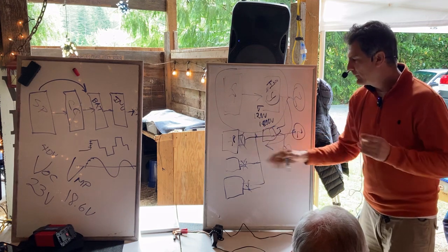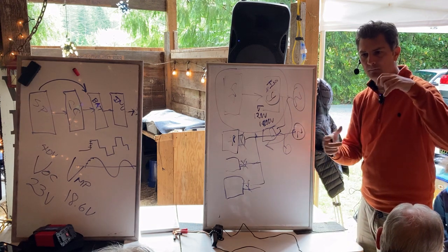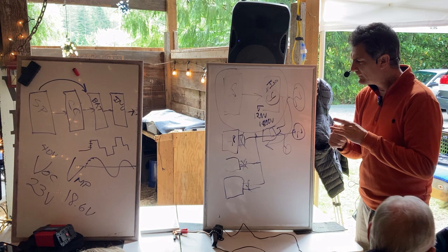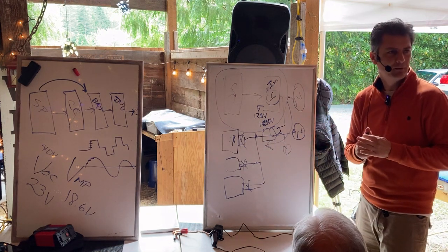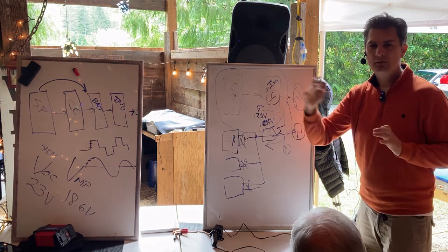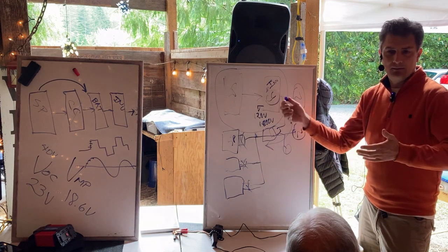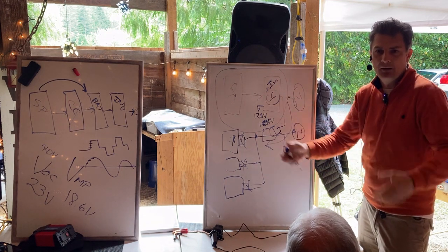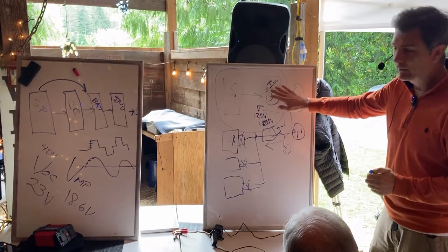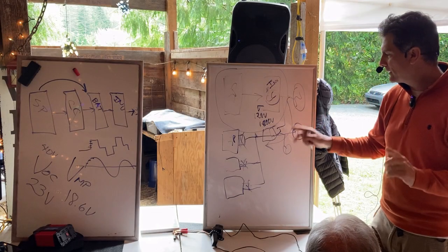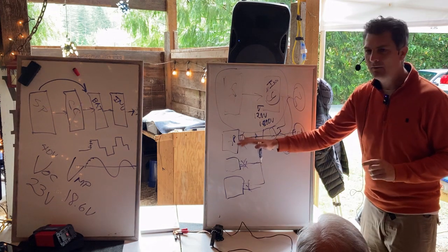The other thing is, if a microinverter breaks, you have to find that panel, take the panel up, get under there, swap it out, and put a new one in. I'm not a big fan of microinverters anymore. I loved them when they first came out, but with options in the future, when you put a microinverter on every panel, you don't have any options. You have to take them out later if you want to go to a battery backup.